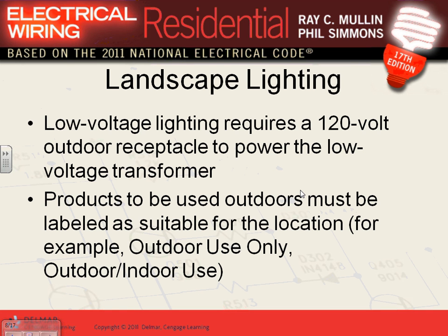Low voltage lighting requirements. Most of the time, guys, you have a low voltage system, you plant these lights. You've seen a couple of pictures of them. They're 120, they come from an isolated transformer, and it feeds all these lights at 24 volt. I had my neighbor one time, I always tell this story. He was doing his lights and he was tying the wires on the lights. When he was tying these wires, he was tying the hot and the neutral together. So he kept blowing and burning that circuit, the isolated transformer. Twice he went to Home Depot to buy one, and he burned it, until finally he came to me and said, "There's something wrong."